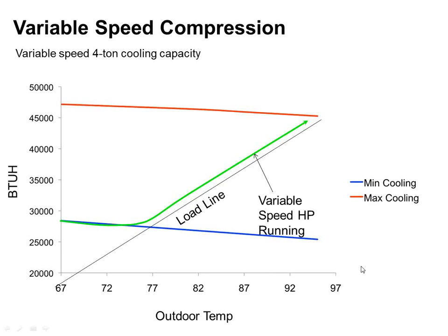The nice thing about a rotary is it's inherently more efficient than a scroll. There's less internal friction, so it saves more energy overall. But it doesn't really allow me to overspeed it. So I can typically have a better turn down range with a rotary, and better cooling efficiency, but I can't really get there on the heating side. If you're looking at a cooling only application, a variable speed rotary is probably a smarter choice, assuming everything else is equal. If I'm looking at a heating dominated application, a variable speed scroll might end up being the better choice, especially if my other heating choice is electric resistance or propane, then it's kind of a no-brainer.